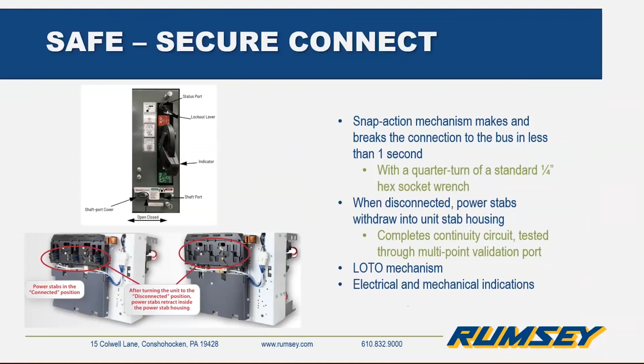It's right above the disconnect handle. So now you basically have mechanical and electrical indication that the unit is disconnected from power. There's even an additional lockout tagout lever that can be used, and that's in between the status port and the disconnect handle. And the door, basically throughout this whole process of removing or replacing buckets, the door remains attached to the MCC and closed. So, again, you're just limiting exposure to live electrical parts and hazards while doing this maintenance on it.